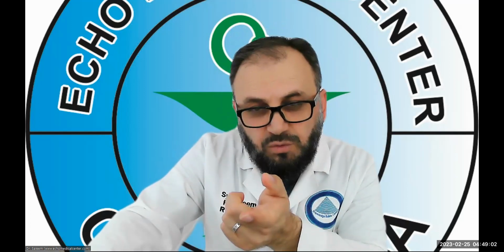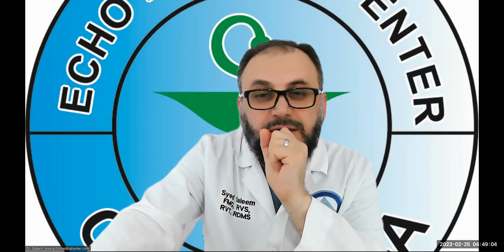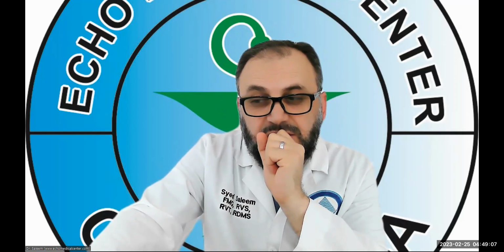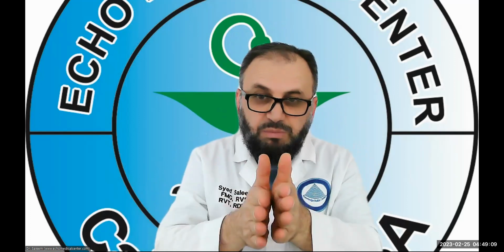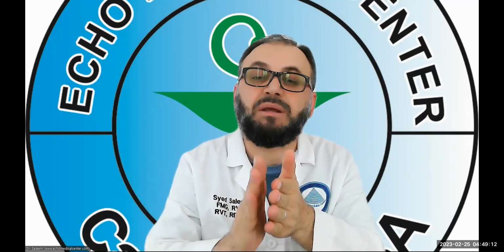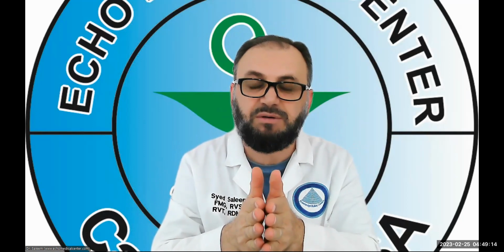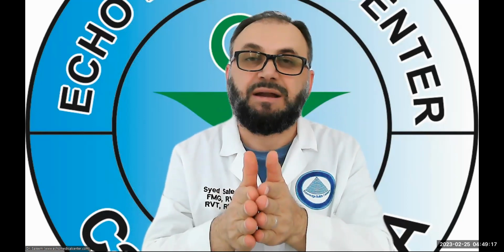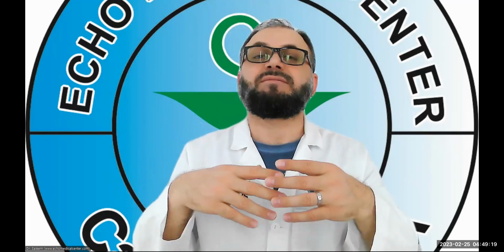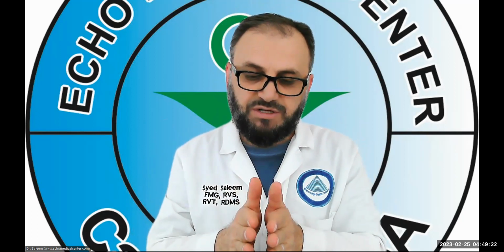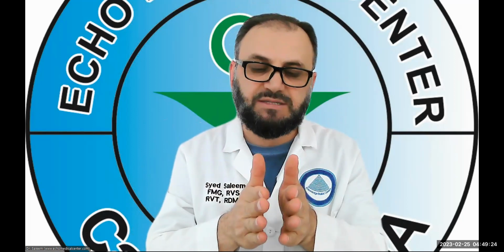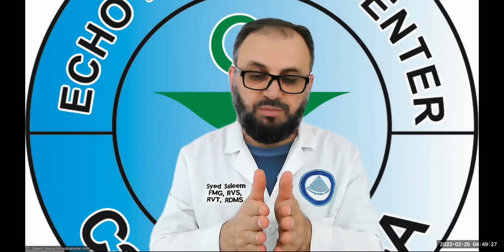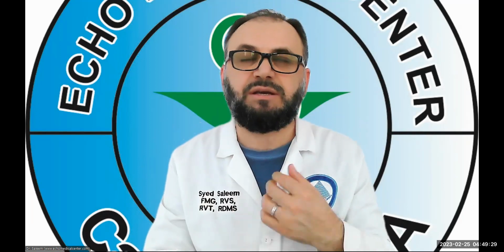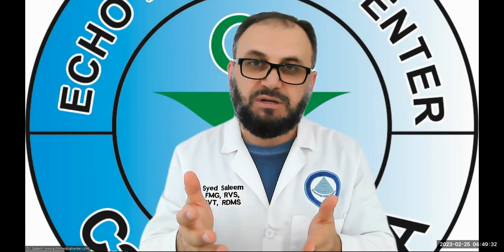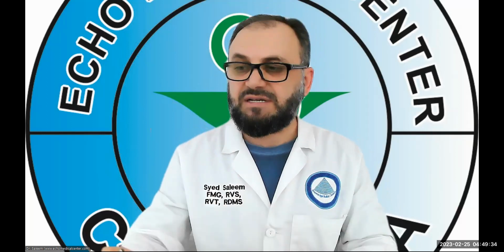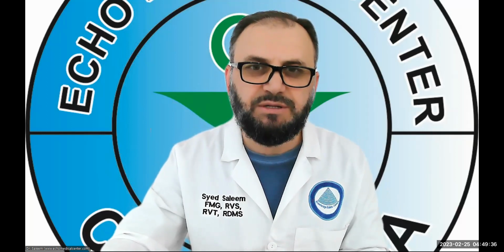Now, the other one, number 5, I believe. That assumption is, we said the sound beam is a thin beam. The beam of the sound has to be very thin. That's the assumption. If it's dilated, so any sound beam that is more dilated, or we can say a wider beam, the easy way to say is that lateral resolution is degraded. So what happens on that? Let me explain that also a little bit quickly.